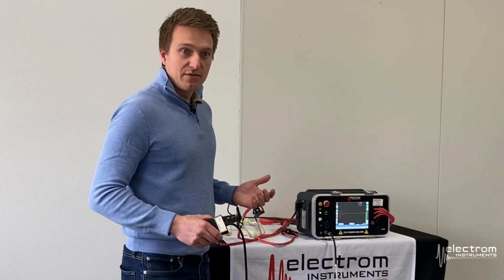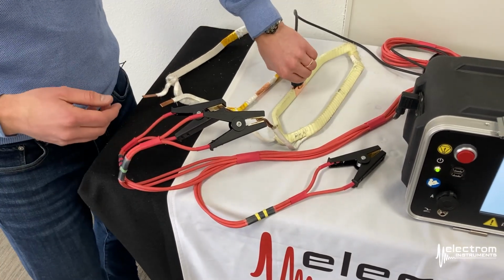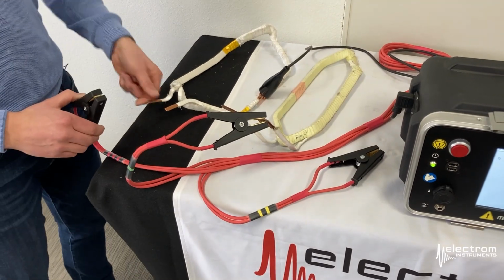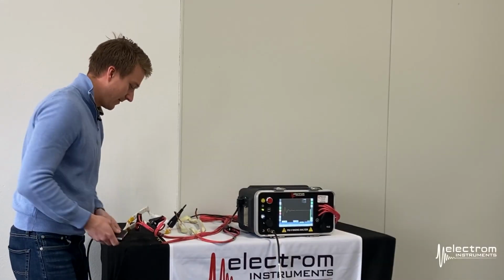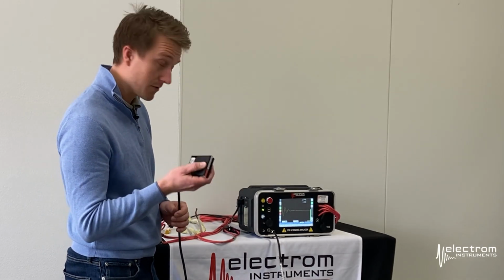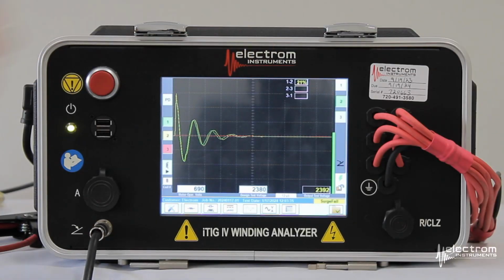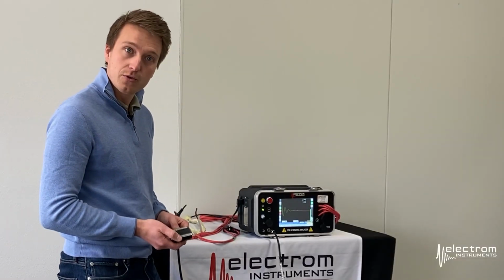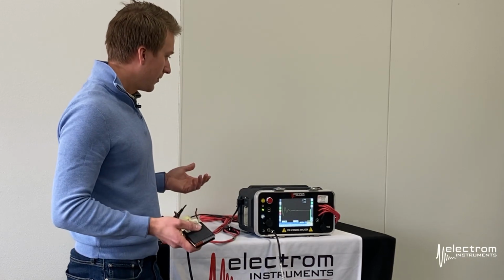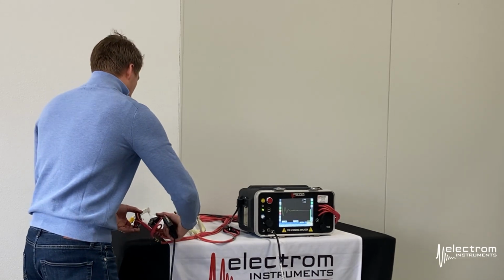In the event that you have a fault, which we are going to show by connecting to our second coil here, moving our leads over. And again, we have our next coil already selected automatically. Press and hold the foot switch, runs the test, and we now get a 21% wave difference versus our first coil, the golden unit in this case, and a surge fail. So we know, okay, this is not a good coil. We move on to the next coil in the coil set.